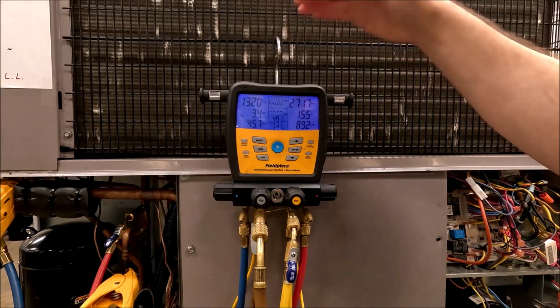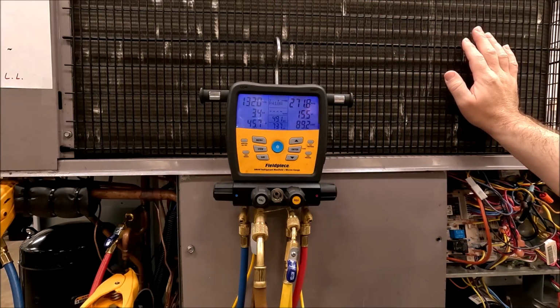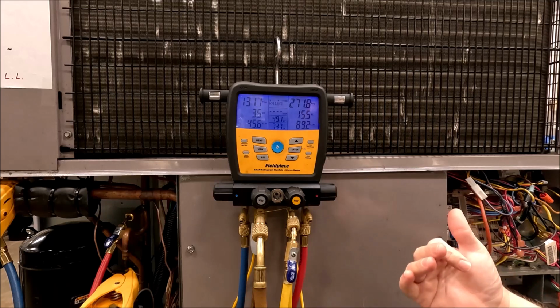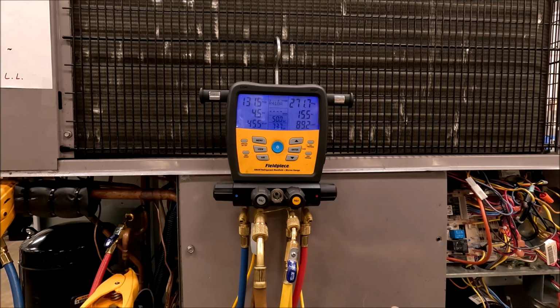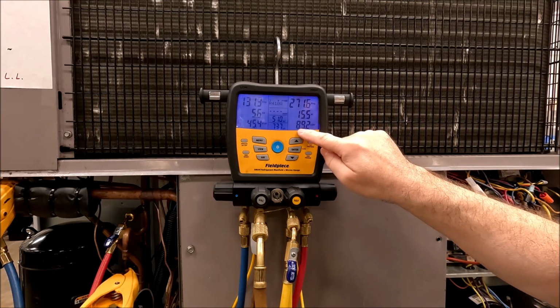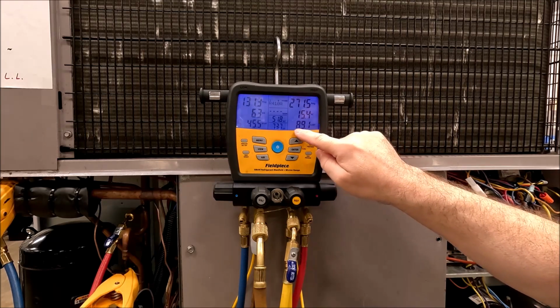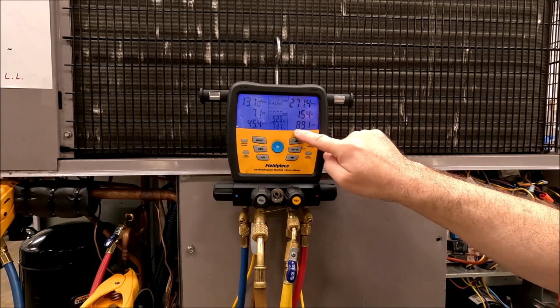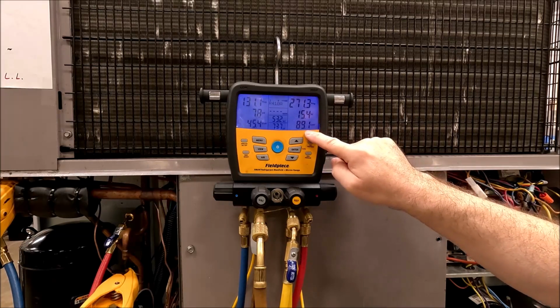The condenser side, this being a 15 SEER according to the model number, 71 Fahrenheit, right? We're gonna add about 15 to 20 at the high end. We should have been around 90 degrees, 91 degrees on my saturation point, and I am. I mean, 89.1, I mean, that's pretty close.